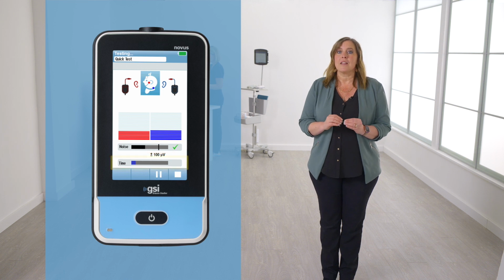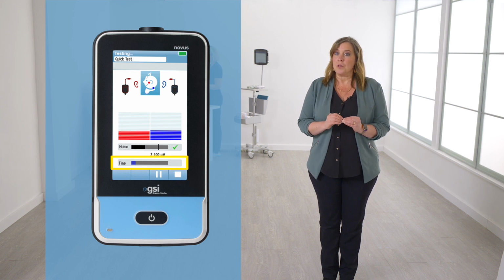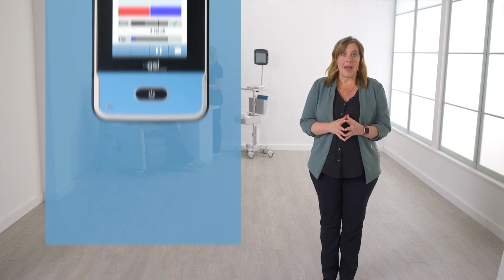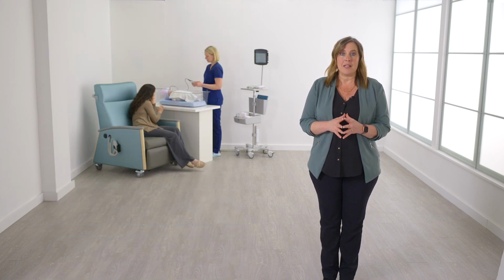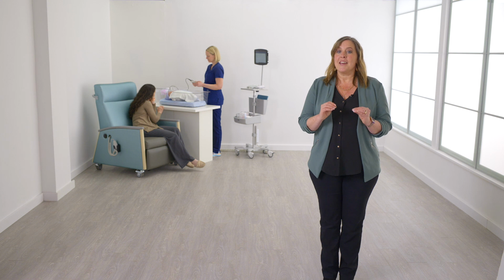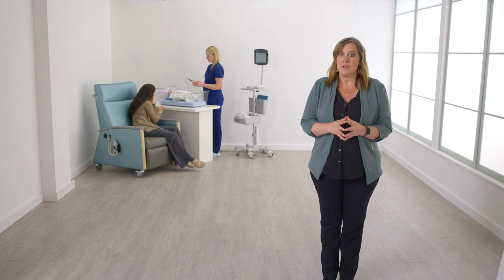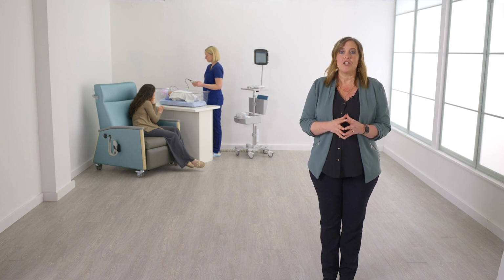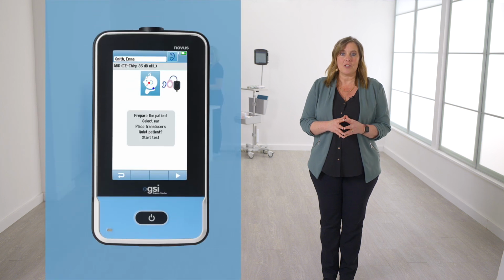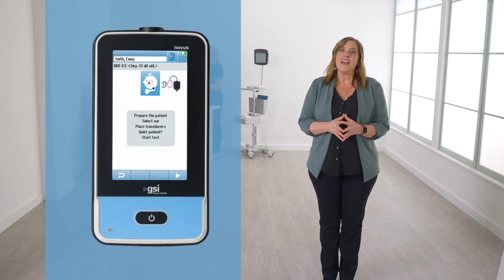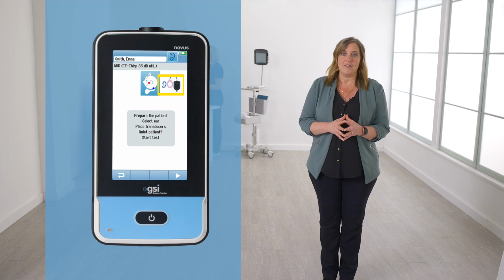Third, the time bar is a progress bar to keep track of the test time. The test will last a maximum of 3 minutes. The test will conclude when both ears have met the criteria for a pass result or the maximum time has been reached. It is possible to test one ear at a time when using the ear cups or ear tips. Touch the ears icon on the top right of the screen to toggle to the test ear. If you are using the OAE probe for ABR, a single ear icon will be visible and will toggle between right ear and left ear. The right ear is red and the left ear is blue.